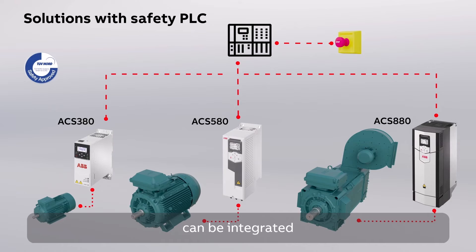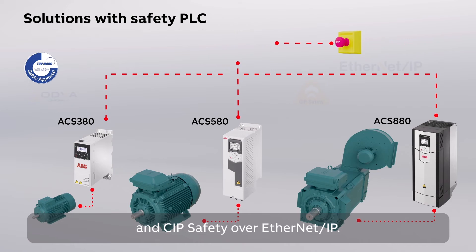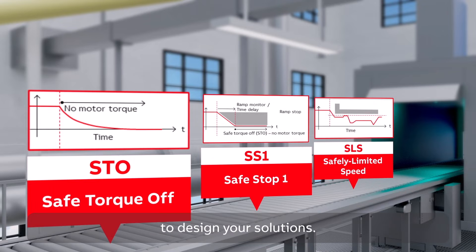A network of drives can be integrated with functional safety together with a safety PLC. The safety PLC is connected to the drive with PROFISAFE over PROFINET protocol and CIP Safety over EtherNet/IP. You also have several certified safety functions from which to design your solutions.